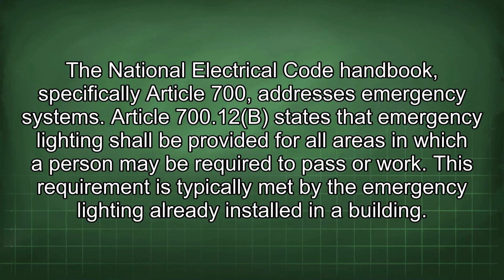The National Electrical Code Handbook, specifically Article 700, addresses emergency systems. Article 700.12(b) states that emergency lighting shall be provided for all areas in which a person may be required to pass or work. This requirement is typically met by the emergency lighting already installed in a building.